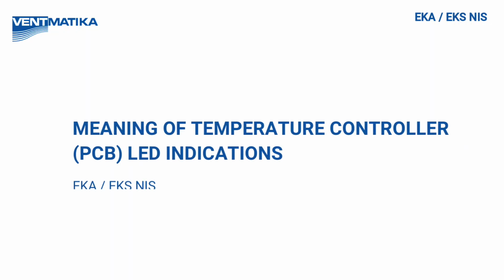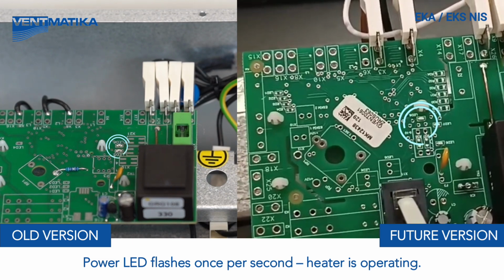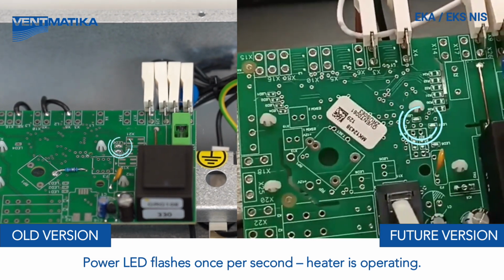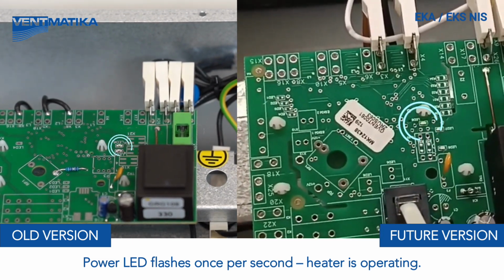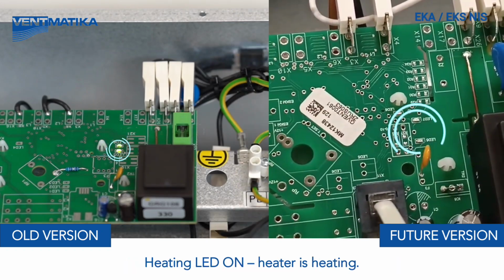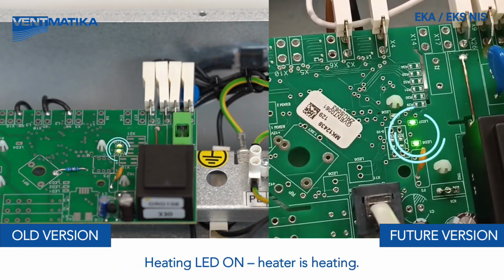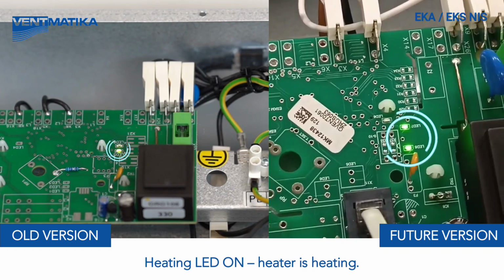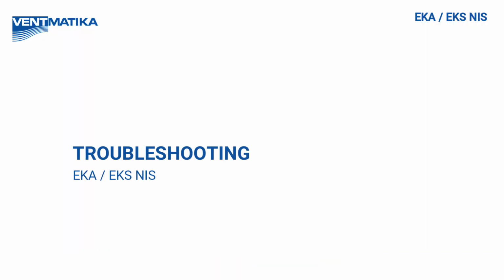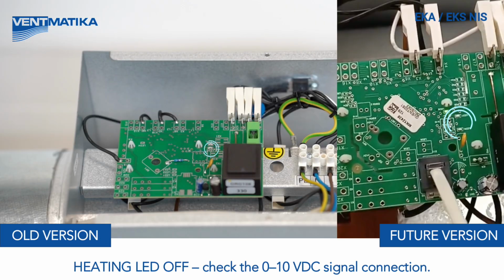Meaning of temperature controller LED indications. Power LED flashes once per second: heater is operating. Heating LED on: heater is heating. Troubleshooting. Heating LED off: check the 0 to 10 volts DC signal connection.